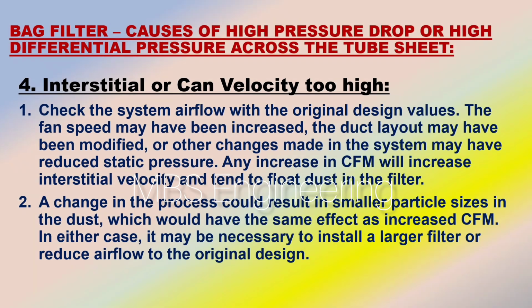Point number 2. A change in the process could result in smaller particle sizes in the dust, which would have the same effect as increased CFM. In either case, it may be necessary to install a larger filter or reduce airflow to the original design.